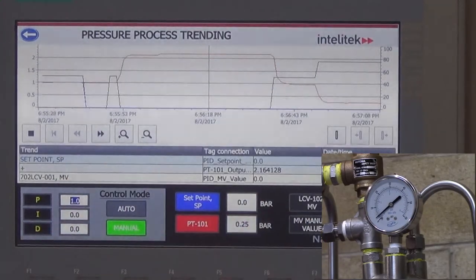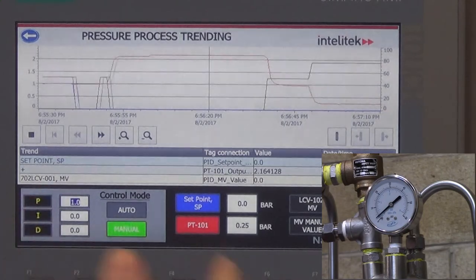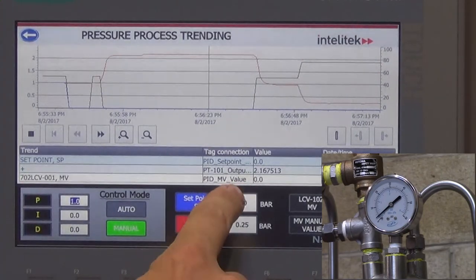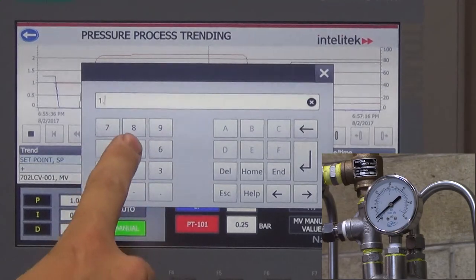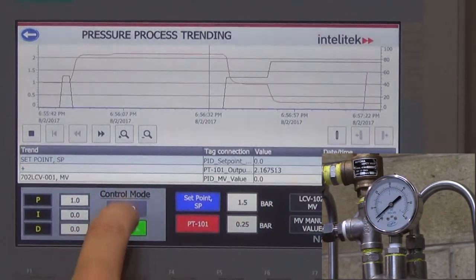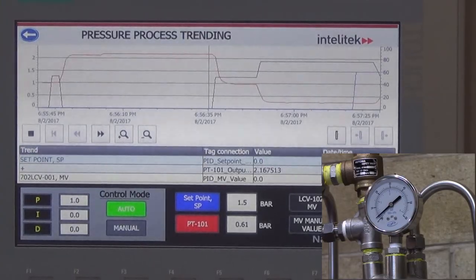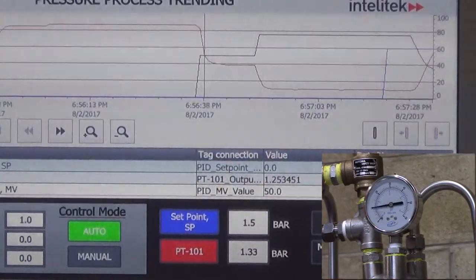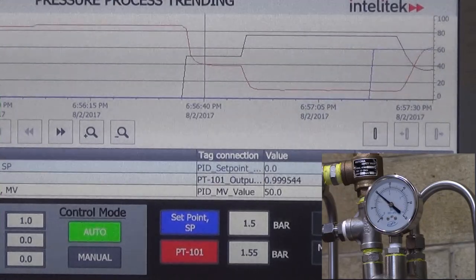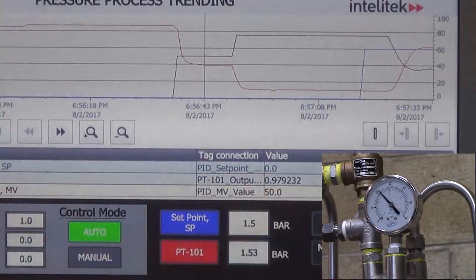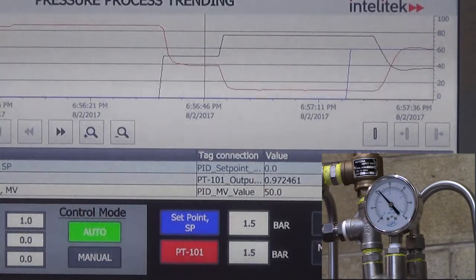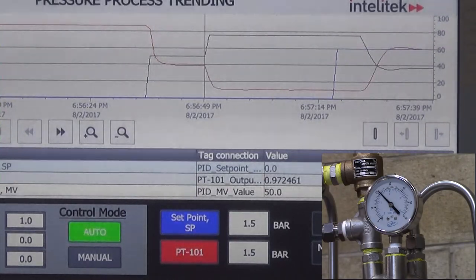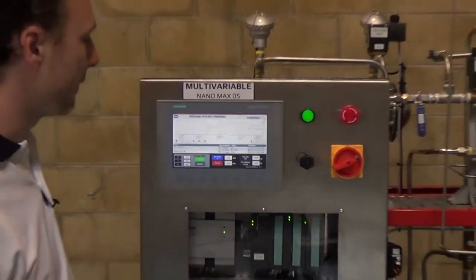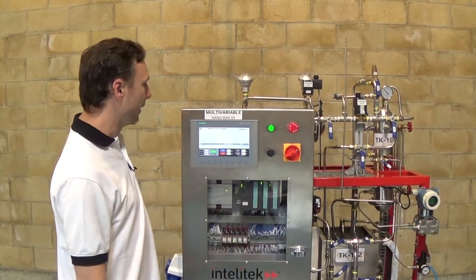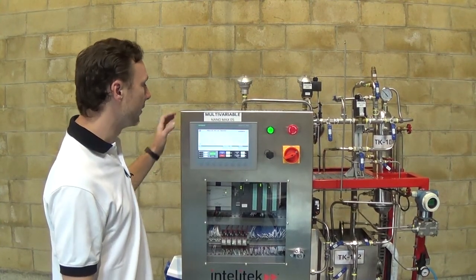And again, if I want my air system to run at a certain air pressure, I can set a P, I, and D value, or just a P value for this case. And I can say I want 1.5 bar of air pressure, set it to automatic. And we can see the graph of it quickly matching my demand and request. And now we currently have 1.5-ish bar of air pressure inside the system. Seems like a very simple experiment, but it really gets the job done for trying to teach process control with air pressure.